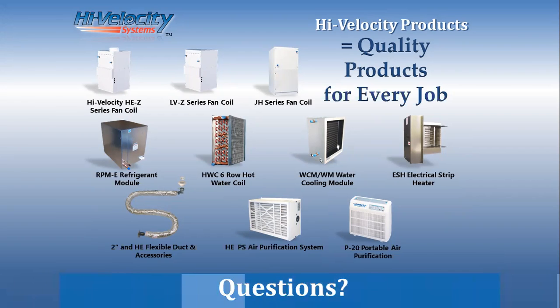Hi, Tim. We do have a few questions on here. That was really great. Thank you. So the first question is, how does the cost compare to conventional systems? Great question. If it's a one-off installation, we typically come out 10 to 20% more, material to material. A lot of that is because my pre-insulated flexible duct is more expensive than the 4, 5, and 6-inch tin that you would be using on traditional ductwork. The equipment itself is pretty close. When we get into projects that we're doing multifamily and multiple units on a site, we do get very aggressive with our pricing to meet the exact costs of your traditional installation, be it a Goodman furnace or a Trane heat pump. We get really close to that number so that we can get those larger projects.